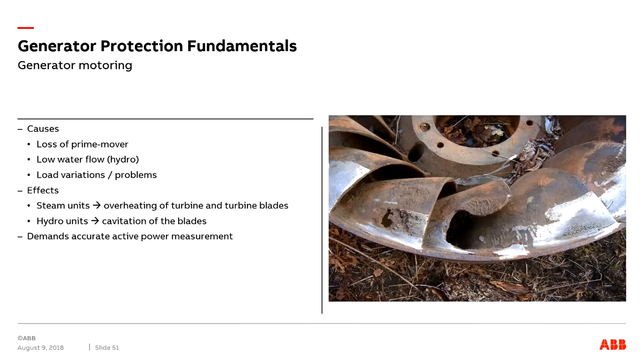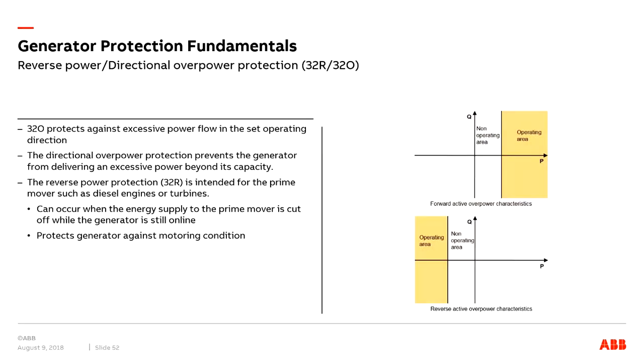It can be caused, as we said, by loss of prime mover, low water flow in the case of hydro systems, load variations, etc. The effect can be overheating of the turbine and turbine blades, and it can cause cavitation of blades in the case of hydro units. So this protection demands accurate active power measurement. This is a method we use to detect such a situation.